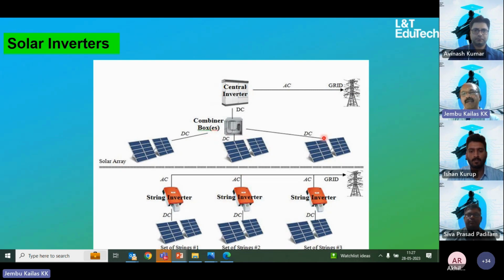You take all these, or you can say pooling, you pool all these things, and it is going to the central inverter. Similarly, you have got a string inverter, that is a decentralized one. Some groups of inverters you can have, rather than keeping central. Here itself you can have group inverters, and you can have this AC connection, and you can take it to the grid. Here you should understand that the duty of the inverter is not only conversion, it acts as the brain actually, because this is what gets synchronized. Through the inverter only you are synchronizing your system to the grid.